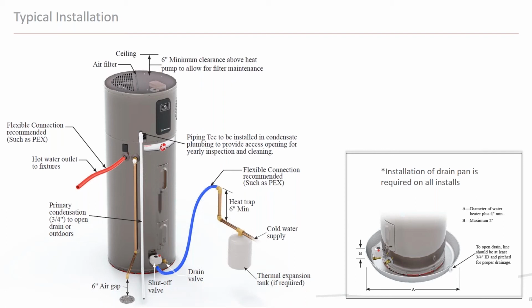And then you can just earthquake strap them in. Other manufacturers, check their use and care manuals. Some require an 8-inch service space all the way around the unit. That means you have to channel block and strap the unit 8 inches off the wall, which means sometimes you have to build out the pedestal. Just take a look at the use and care manual to see what those requirements are going to be.